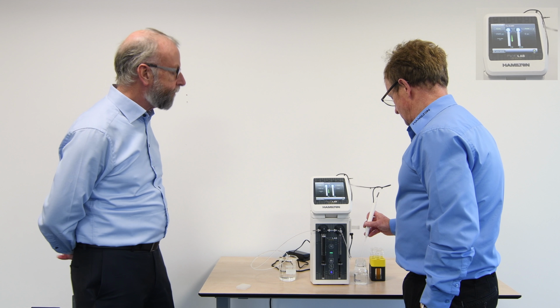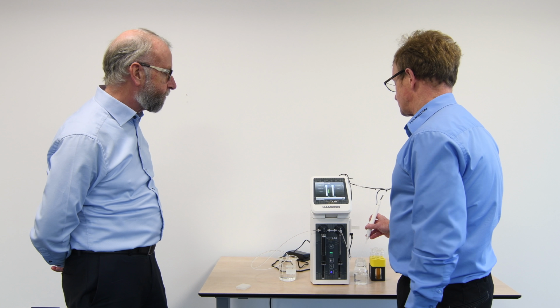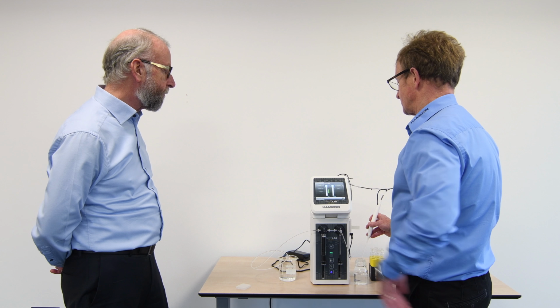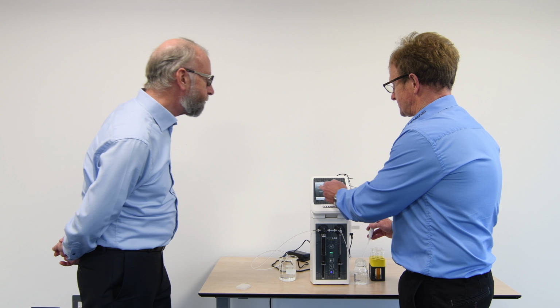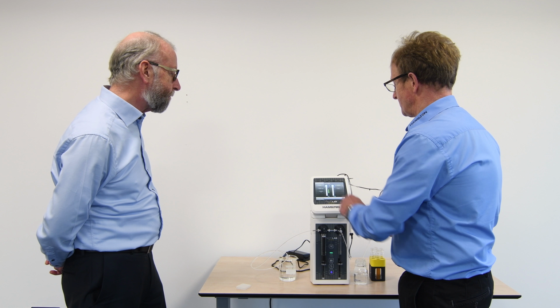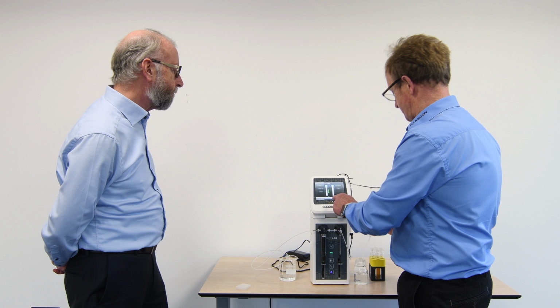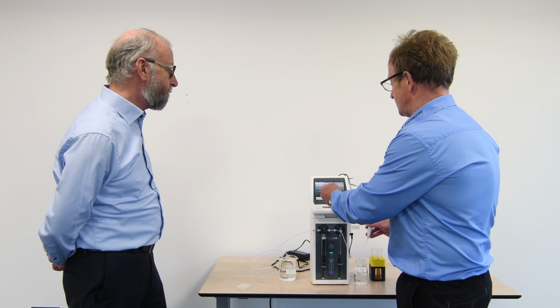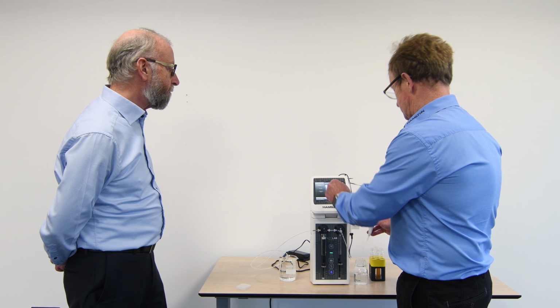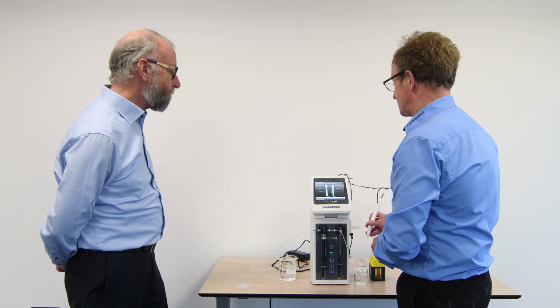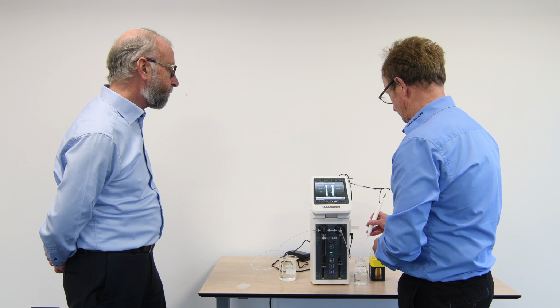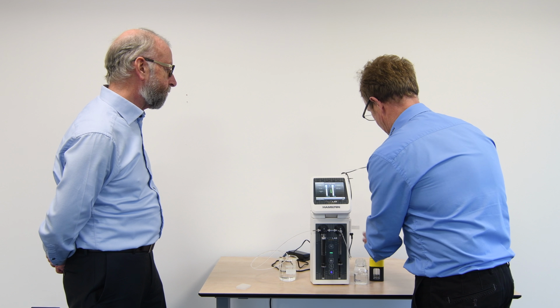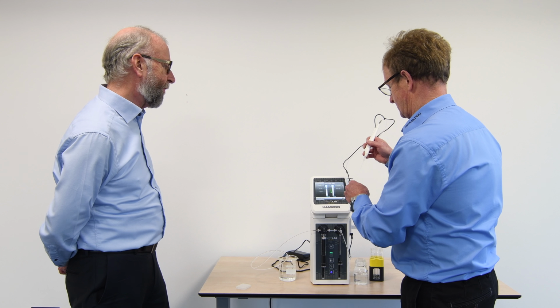Exactly. Okay. So the thing that we've done here is added some additional text lines. You remember the arrow is showing us here that we're going to be filling with diluent, but we've put a text line to say what that step is. So here, by initiating the first step, you can see it's taken the diluent, and now it's told the user what the next step is in terms of aspirating sample. So that makes it foolproof, really.